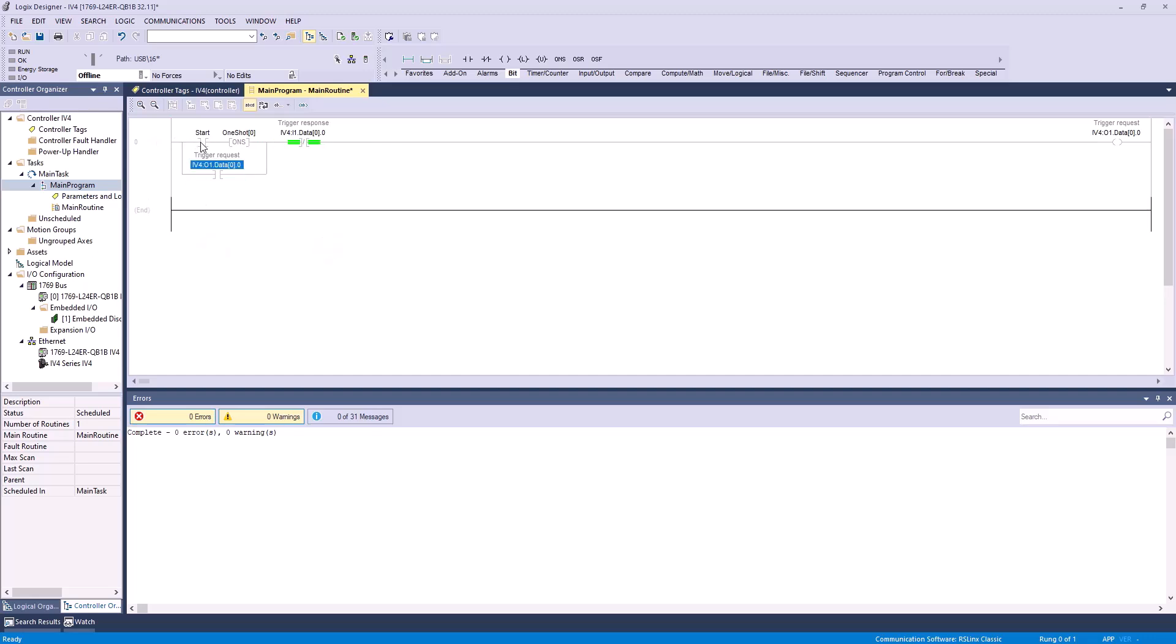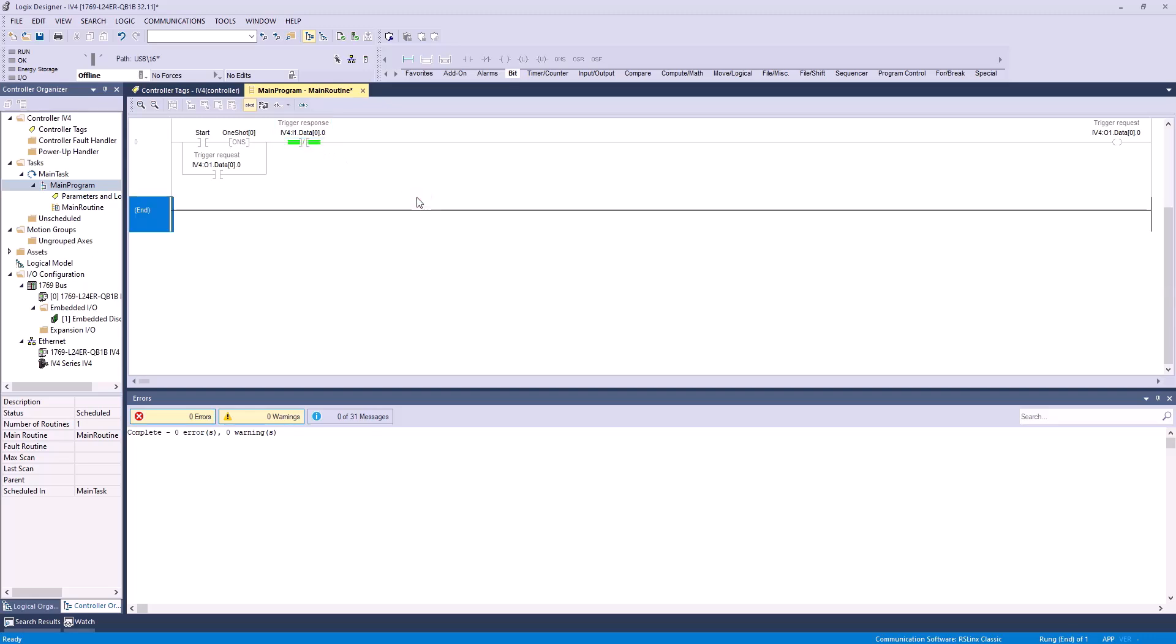This means that if we start it with our dummy start bit, or if the trigger request bit goes high, it'll send this through here. By having this trigger response examine if open bit here, this creates a self-latch circuit where we're making sure we're not going to be sending two trigger requests too quickly, and we'll make sure we don't have any errors popping up in our IV smart navigator software.